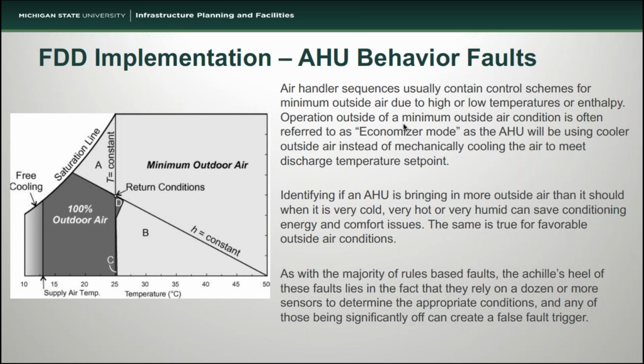So I wanted to give you a little taste of some of the more complex faults that we've put into place. One of the most common sequences that are in place on an air handler is commonly referred to as either economizer mode or free cooling. And the idea is that if I want 55-degree air to come out of my vents to cool a space, then I want to use the least amount of energy possible to hit that 55 degrees. So if my outside air temperature is also 55 degrees, I don't want to bring any air back from the space, and I don't want to heat or cool that air at all because I'm essentially just bringing it in without having to do any comfort conditioning on it. And so we save some energy associated with that. The downside of this is we rely on a lot of sensors in order to detect these conditions. So are we in that happy medium where we want to bring this in?